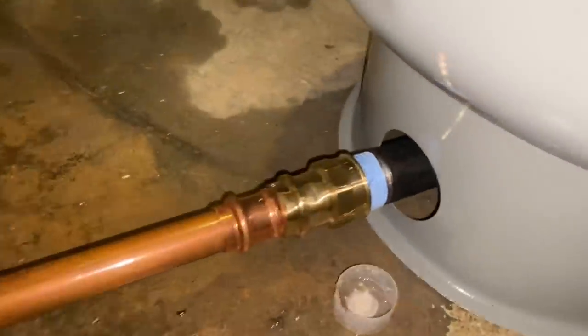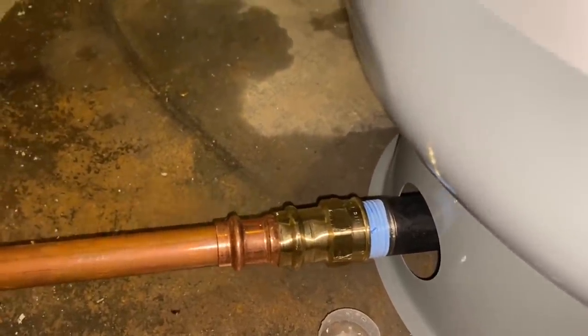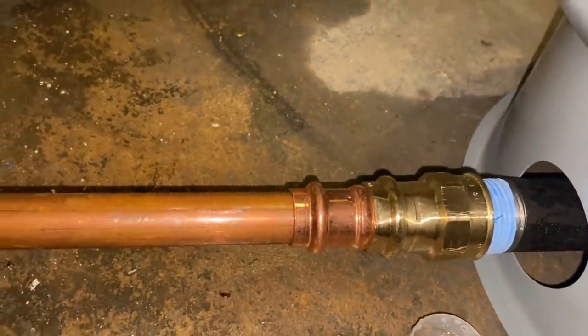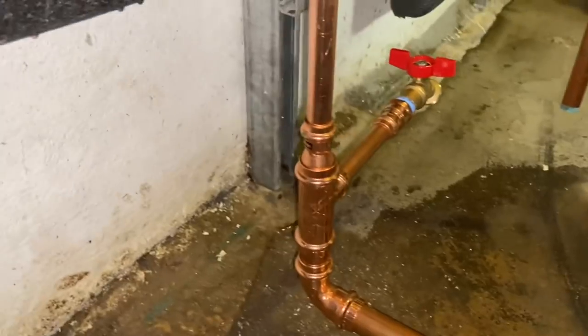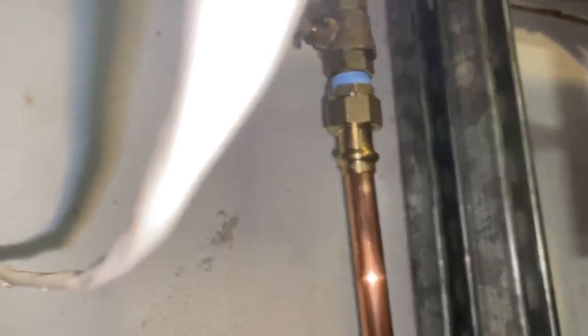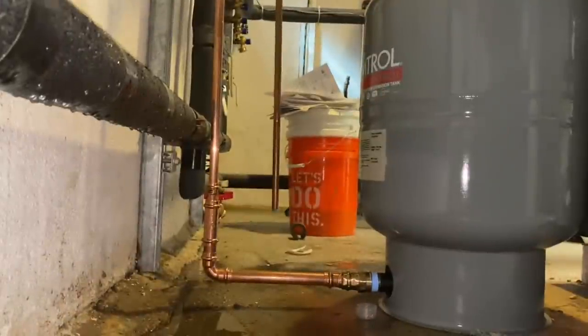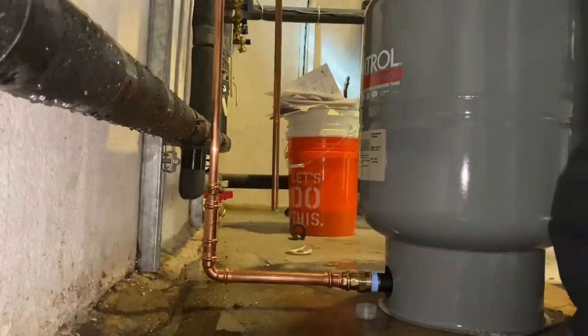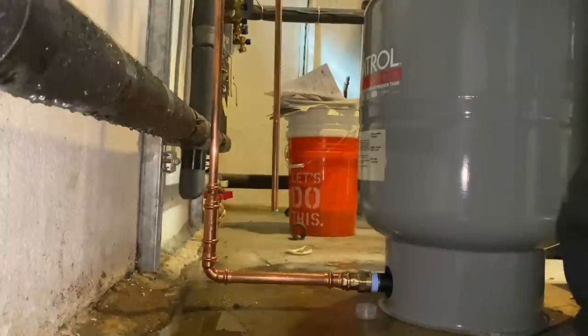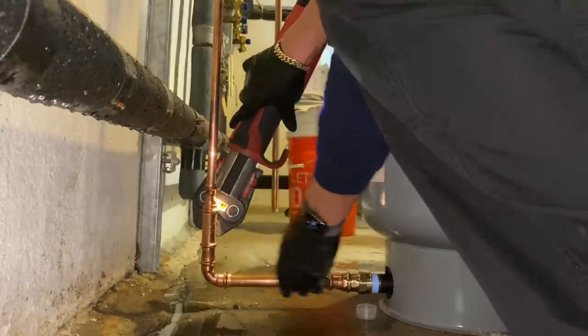Mikey describes the piping configuration: one-inch black nipple coming out of the bottom of the Amtrol SV30, one-inch Viega female adapter, a slip reducer to three-quarter, a 90, a one-inch by three-quarter by half-inch tee for a drain, a slip reducer, and a union right below the already installed connection. He was going to press all this in and got his press machine into position.